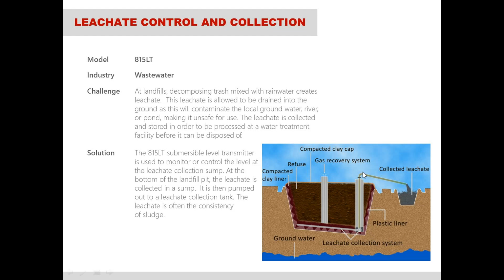And so that leachate cannot just be dumped back into the ground. You have to collect it and properly treat it before it can be sent back into the ground, because it can damage the environment and the local drinking water where it's disposed of. So you have to collect it inside the leachate collection system, and you'll have a transmitter there to monitor that level, as well as where it's being collected and stored before it's sent to a water treatment facility.